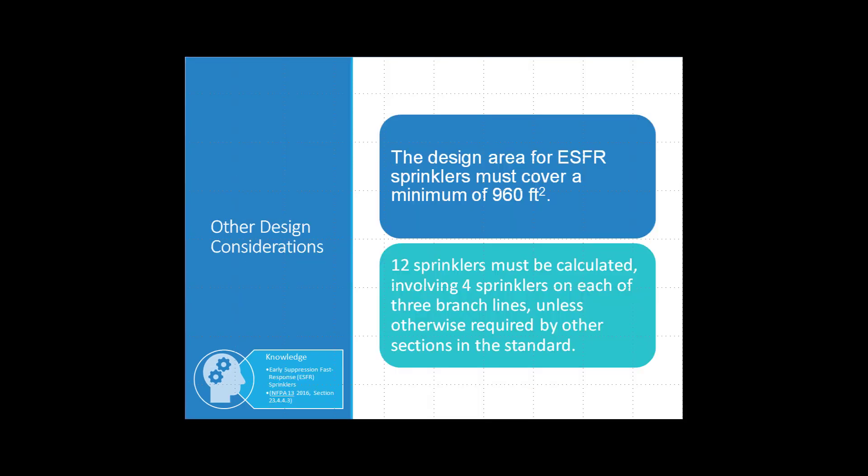The design area for ESFR sprinklers must cover a minimum of 960 square feet. 12 sprinklers must be calculated involving 4 sprinklers on each of the 3 branch lines unless otherwise required by other sections in this standard.